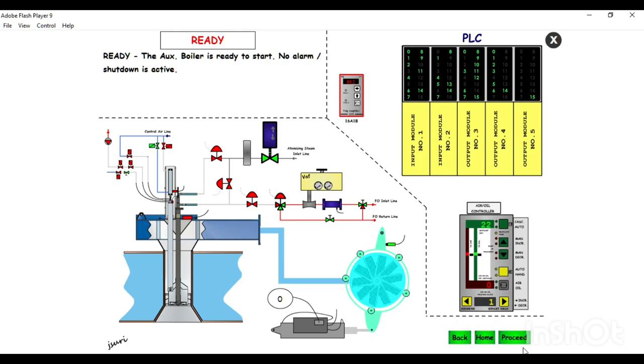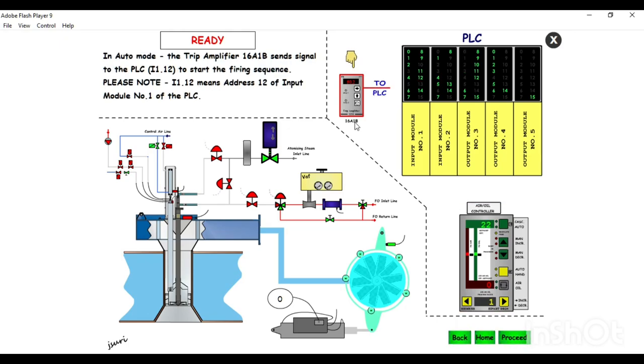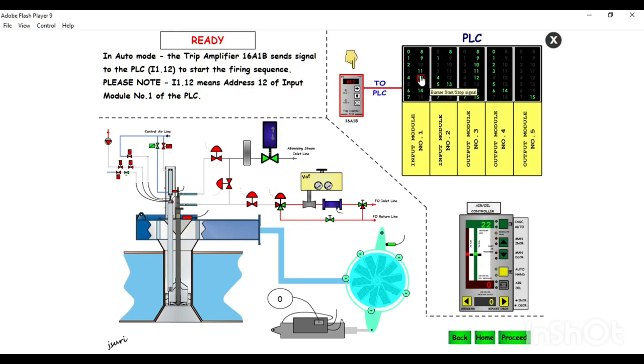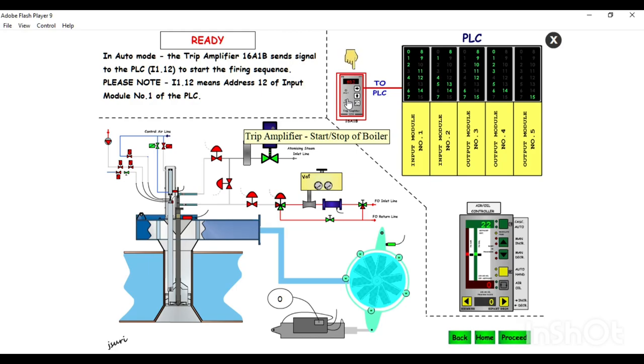The boiler is in start condition, kept in auto mode with no alarm and shutdown present. The trip amplifier has a set point - once the steam pressure reaches that value it will send a start signal to the PLC. From the trip amplifier, the start signal goes to input number 12 of the PLC, which is for the burner start and stop signal. Once received, the start sequence is initiated.